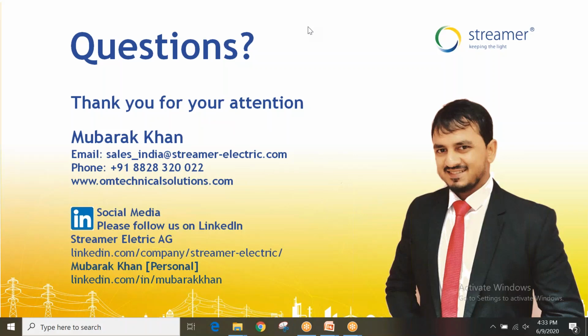Any further questions? Suppose in the adjacent panel where a cable is connected, a fire breaks out and affects this panel — can it be detected? Yes, it will detect. If there's a fire in the nearby panel, the heat will be too much and cause the sticker to burst, releasing sticker gas that the sensor detects. Also, if smoke from that panel enters this cabinet, it will detect that too. So it works both ways.